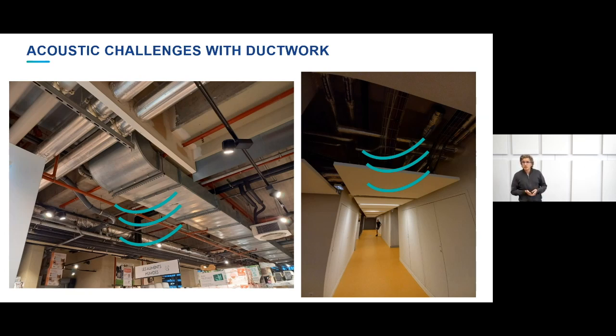And on the right, you have another practical case from Paris-Saclay University, where you can see another ductwork behind the false ceiling. And in this case also, you could say to yourself, okay, maybe sound insulation is not really a problem because I have the false ceiling. But as I told you, and as you can see on the picture on the right, there is some space in the false ceiling. So from the acoustical point of view, it will not be able to insulate correctly. So typically the sound produced by the ductwork, even in the right picture, will be an issue, and a question of sound insulation.